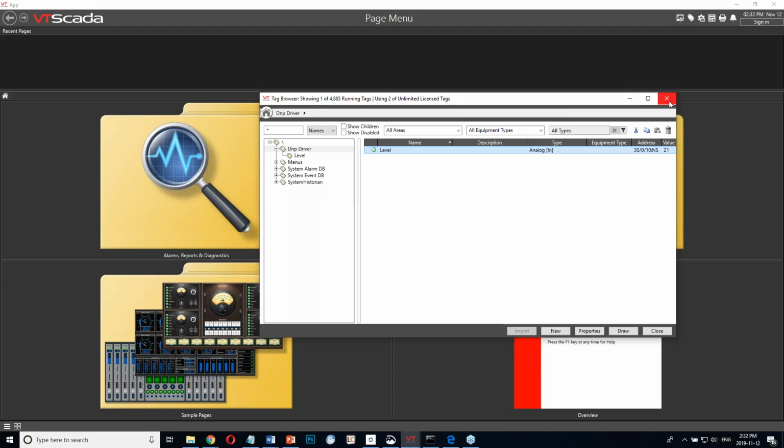When you have this shared communication medium, you've got maybe 20, 100 sites that you're communicating with from the same master radio station, and you probably need to take turns on it because most radio systems interfere with each other if you try and talk to more than one device at a time. And because you need to take turns, you can only poll those stations once every 5 minutes, 10 minutes, 15 minutes. It depends on the latencies in your system and how often you need the data and all of that. So I'm just going to hop back into here.